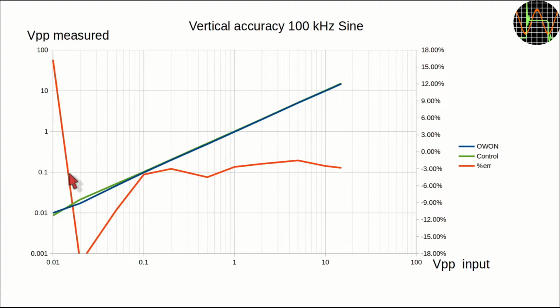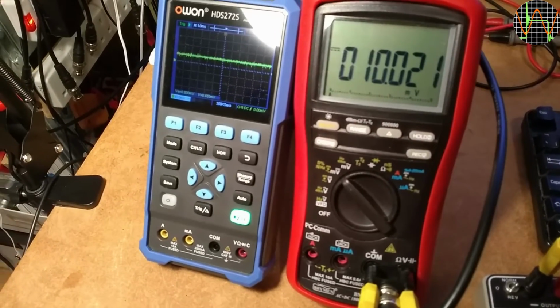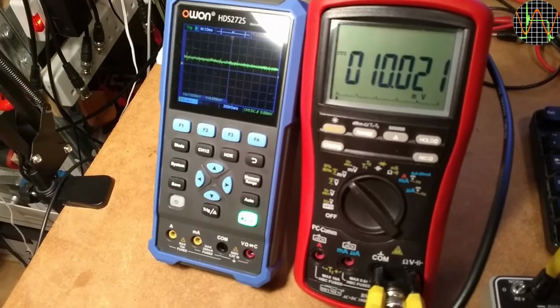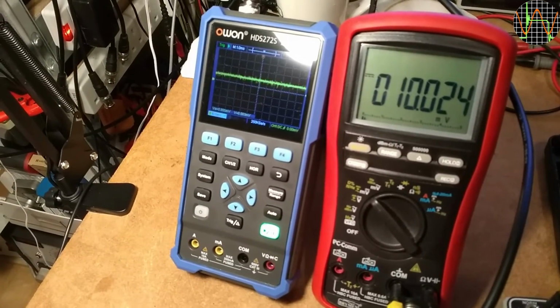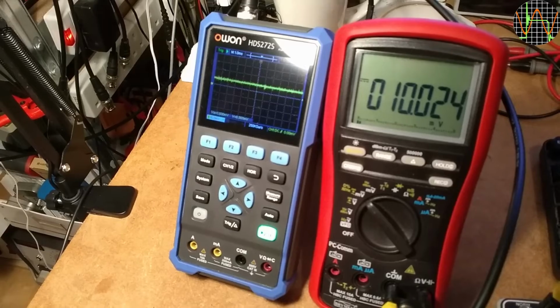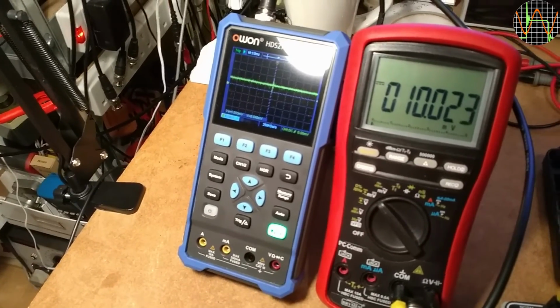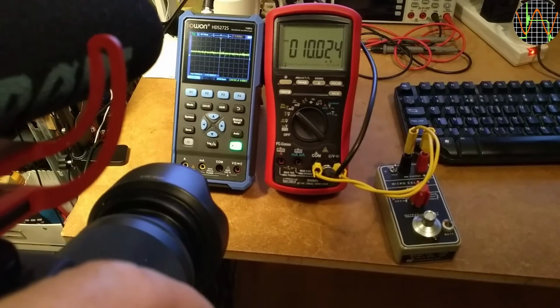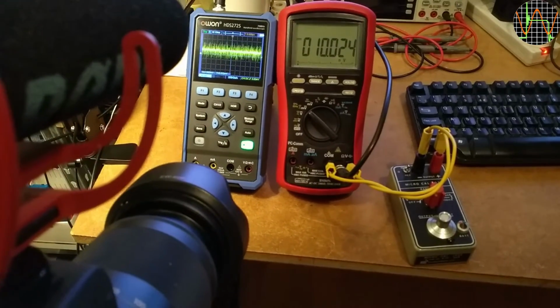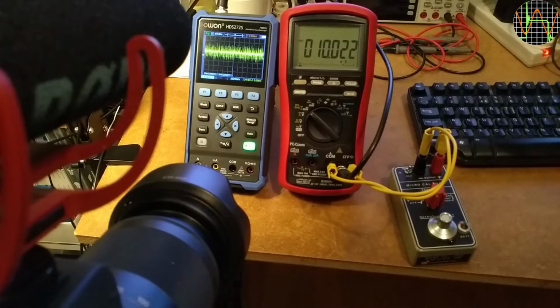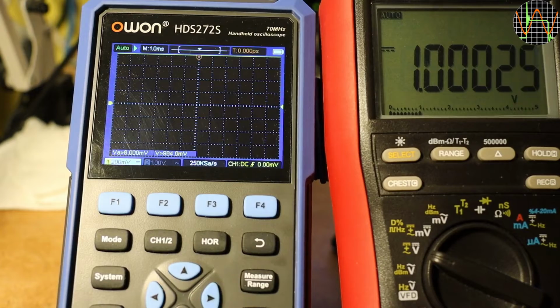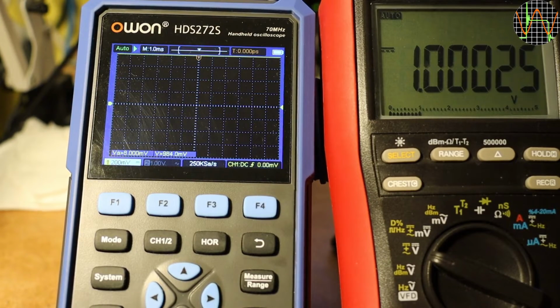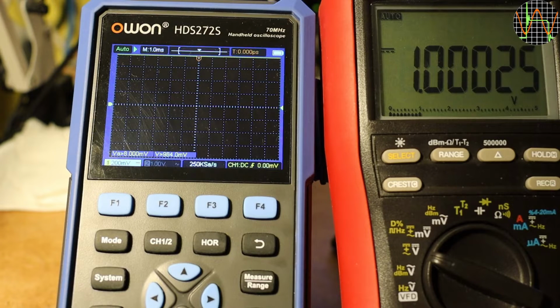For completeness, I decided to measure the vertical accuracy in DC, although one has to wonder how often DC is measured with a scope, but I ran into problems. Here I am feeding a clean 10 mV DC signal into the OWON and the Brymen BM869s as control. The video is very shaky because I'm holding a tablet to film this. Watch what happens when I switch the main camera on. The OWON is extremely sensitive to noise, in this case from the DC to DC converter I'm using to power my camera from a USB bank. At higher voltages like 1 volt here, I can use my main camera because the noise is now invisible.